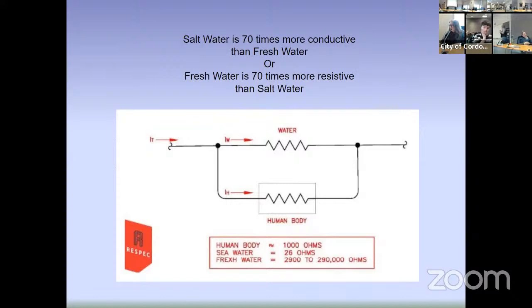This is something I was talking about a little bit earlier. This is explaining why current in the water is a problem. First of all, salt water is more conductive than fresh water. Fresh water is where we have the problem. This is an electrical diagram showing that the resistance of water is one number and the resistance of the human body is another. If you're in salt water, it's more conductive, which means less resistance, and the current is most likely to flow through the water rather than the body. But if it's fresh water, the resistance in the water is much higher, and the body is much lower relative to the water. So you're going to get more current through the body. And that's why we have more freshwater deaths and shocks.